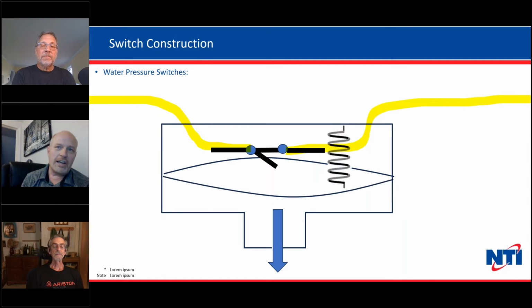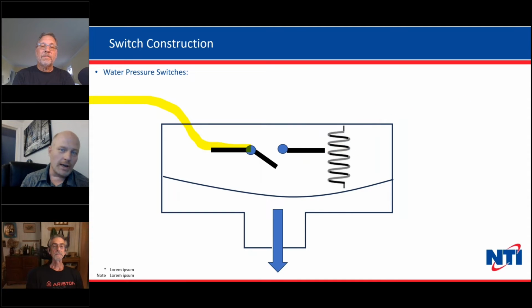Now, of course, if you lose pressure, the spring will push the diaphragm back open, opening the circuit, and whatever safety is getting power from that stops getting power. So that's the water pressure switch. And again, the ones that we use are all normally open switches and they close upon pressure rise.